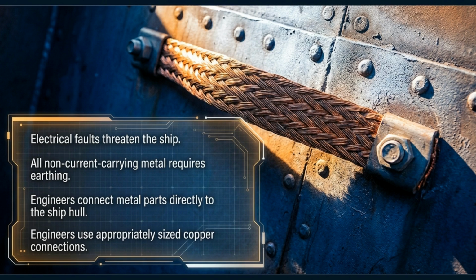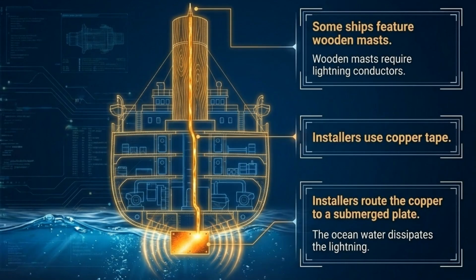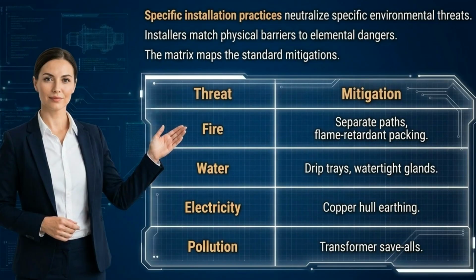Electrical faults pose significant threats. All non-current carrying metal components must be properly earthed by connecting them directly to the ship's hull using appropriately sized copper connection. For ships with wooden masts, lightning protection is mandatory. Installers use copper tape to route lightning energy down to a submerged plate, allowing the ocean water to safely dissipate the charge. This matrix summarizes our core mitigations: separate cable paths for fire, drip trays for water, hull earthing for electricity, and transformer save-alls for pollution control.